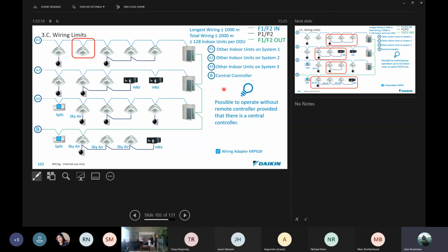And it is possible to operate without a remote controller, provided there is a centralized controller. We've done this before. At commissioning, though, we had to have a set of remote controllers installed. Once commissioning was done, we then connected up a centralized controller and took the wired remotes out. Just a point to consider when this happens: it is always nice to have at least one wired remote somewhere in the system. It's easier to access the system and to see any faults, even if it was just tucked up inside a ceiling near a unit, and marked so that people know where to go to find it.